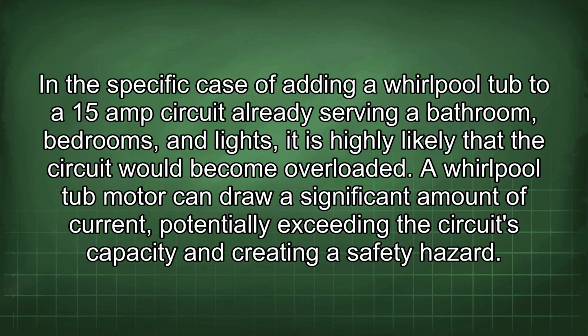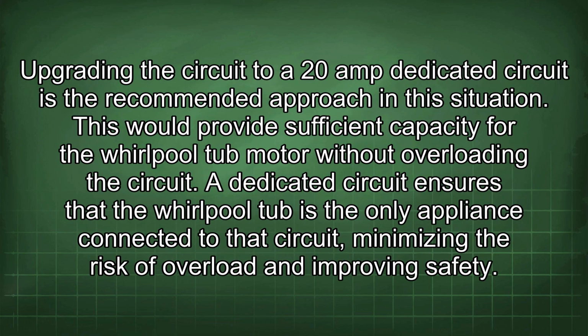In the specific case of adding a whirlpool tub to a 15-amp circuit already serving a bathroom, bedrooms, and lights, it is highly likely that the circuit would become overloaded. A whirlpool tub motor can draw a significant amount of current, potentially exceeding the circuit's capacity and creating a safety hazard. Upgrading the circuit to a 20-amp dedicated circuit is the recommended approach in this situation. This would provide sufficient capacity for the whirlpool tub motor without overloading the circuit.